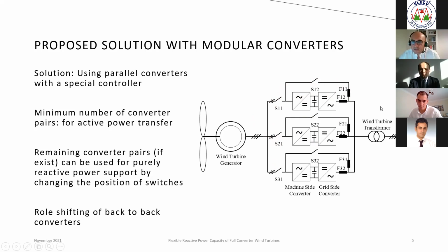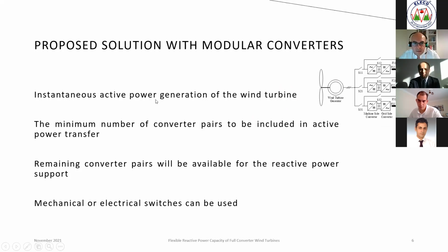Here the control system is easy: we check the instantaneous active power generation, and according to that we find the minimum essential number of converter pairs needed for active power transfer. The remaining converter pairs are then available for reactive power support.